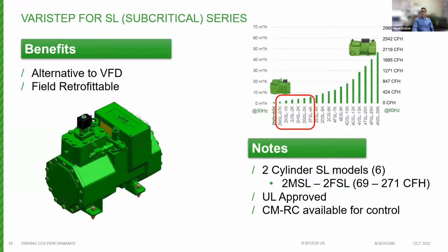BITZER also has a VariStep option for CO2 subcritical compressors, the SL series, for the smallest 2 MSL through 2 FSL compressors. The major difference between this and the TC or TE models is that the SL compressors are backwards compatible, so you could add the unloading option to a compressor that is existing in the field. And again, it's only the 2-cylinder model circled here in red, and there are 6 of those available.